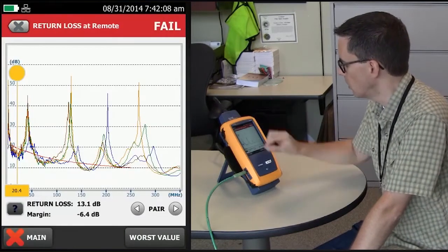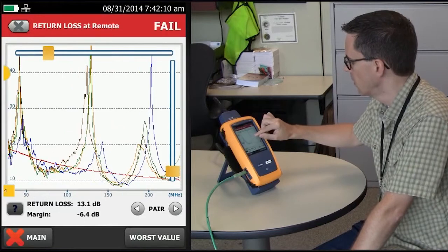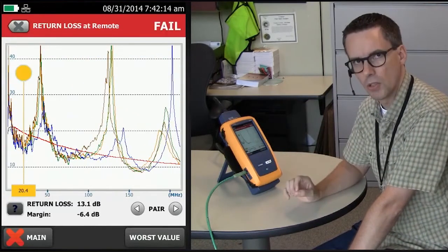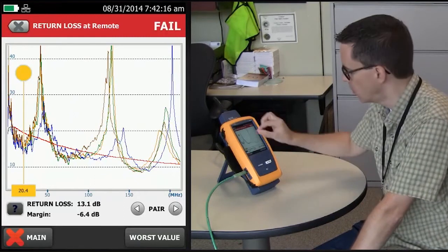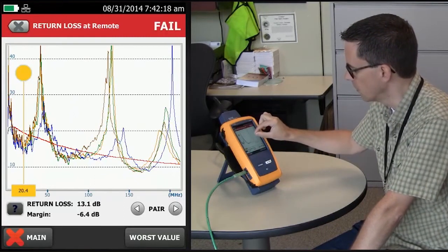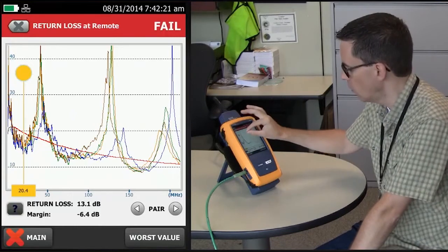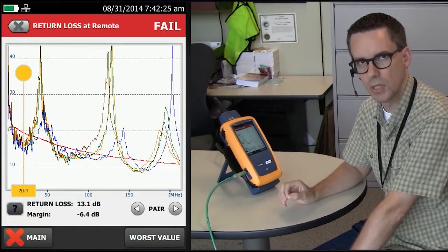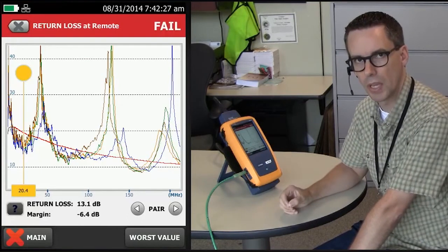Going back to our return loss trace, pinch and zoom in a little bit. You'll notice with this particular trace that all four pairs are pretty much following each other. As a general rule, when you see all four pairs following each other and they're failing, particularly at the lower frequencies, that suggests there's water in the cable.